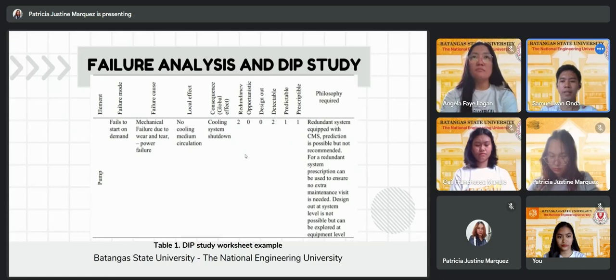A failure mode and effect analysis, or FMEA, shown in Table 1, has been done to gain an understanding of the significance of these components. Also, the DIP research worksheets extend the FMEA studies into maintenance philosophies and their capacity to prevent certain failure modes. To acquire the best result from the DIP study, you need an in-depth understanding of the system and an overview of condition monitoring and equipment control technology. Thus, this investigation should include varied expertise. Process engineers can explain redundancy for pumps and heat exchangers in this case study.